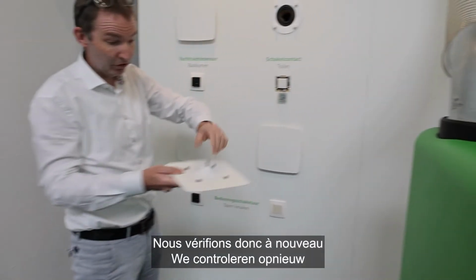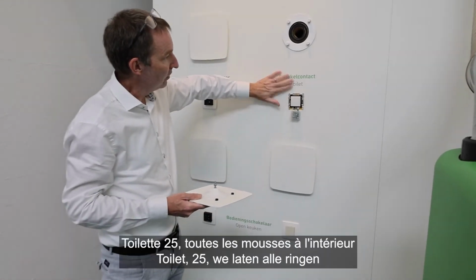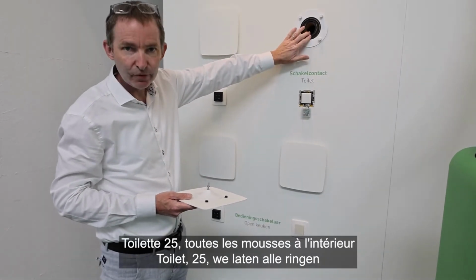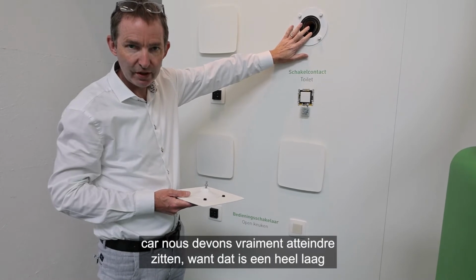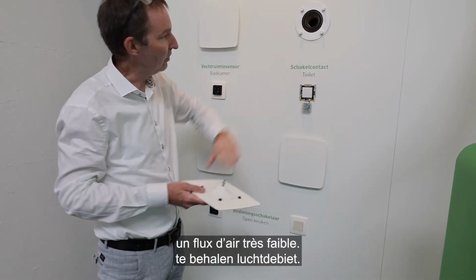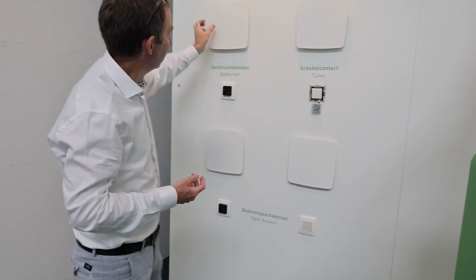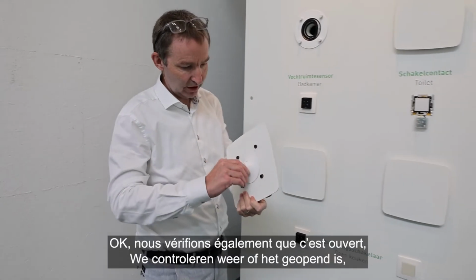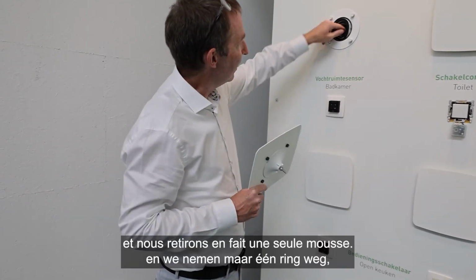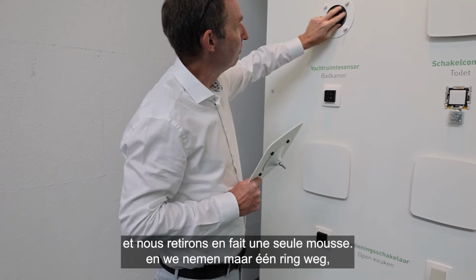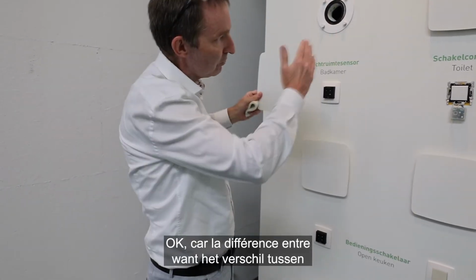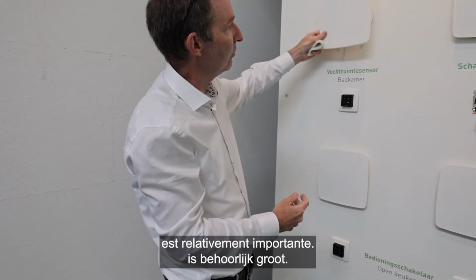So again, we check whether it's open. Here, toilet 25, we leave all the mousses inside because this is a really low airflow that we need to reach. So we leave it in. Bathroom, 50 cubes. We check that it's open again, and we take out only one mousse, because the difference between the toilet and the bathroom is quite significant.